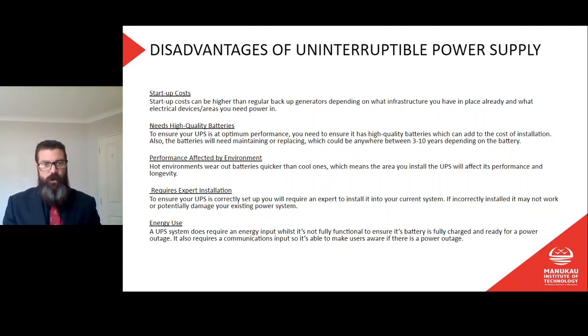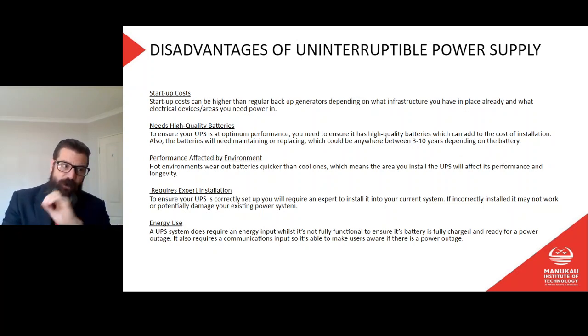So the UPS's job is what? When the power goes off, I supply power. So it's one of these situations where you really need to be very, very switched on with your testing, because the outlets out there may be outlets that remain live even though you've turned the power off, because they are supplied by the UPS.